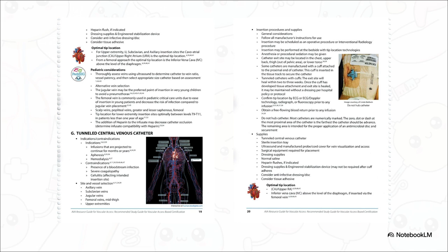And finally, Section 5, hemodialysis and apheresis catheters. This is our highly specialized high-flow access. You guys, these devices are massive. Instead of standard gauges, they're measured on the French scale, which calculates the outer diameter of the catheter. These run from 10 all the way up to 16 French. They're built from highly rigid materials, which is an absolute engineering requirement. They have to be able to handle the intense, rapid blood exchange needed to clean blood during dialysis or extract plasma during apheresis.